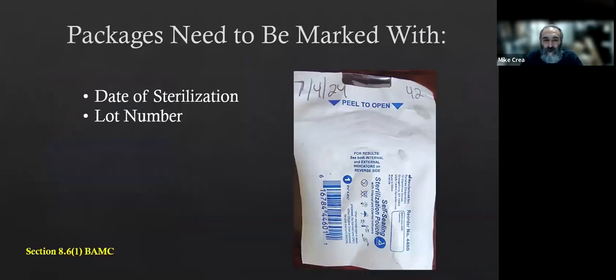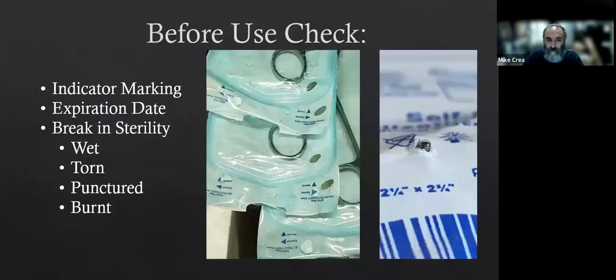When they come out, they should be marked with the date of sterilization and the lot number. So you can see this one we dated for July 4th, and lot number was 42, which would have been the sterilization run that will correspond to the autoclave logbook. So you want to date it with the date of sterilization and the lot number. Before use, you want to check the indicator marking.